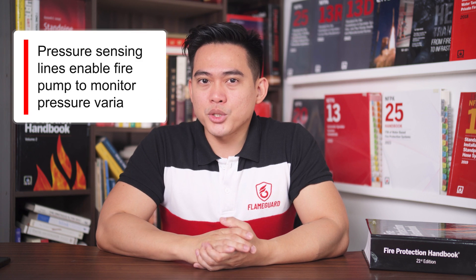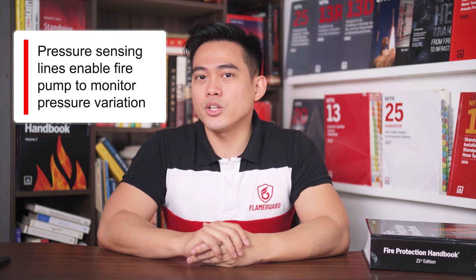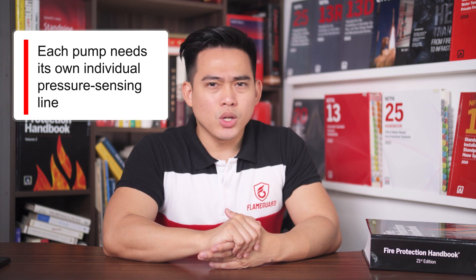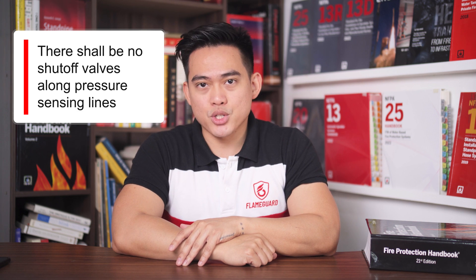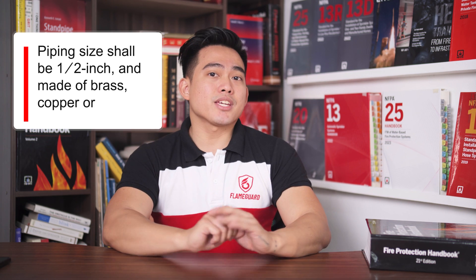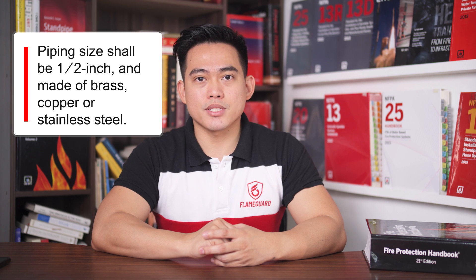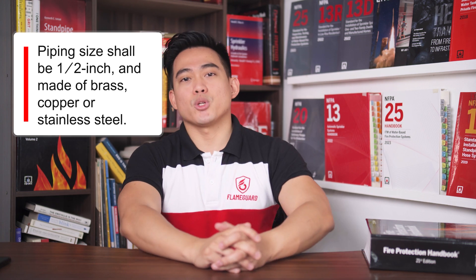Fire pump systems monitor pressure changes using pressure sensing lines so that they can run automatically during a fire. Each pump needs its own pressure sensing line, which shall not be connected in series. There shall be no shutoff valve along the pressure sensing line. The connection for each pump shall be tapped between the pump's discharge check valve and discharge isolation valve. Piping size shall be 1/2 inch nominal, and the material shall be brass, rigid copper pipe types K, L, or M, or Series 300 stainless steel pipe or tube.